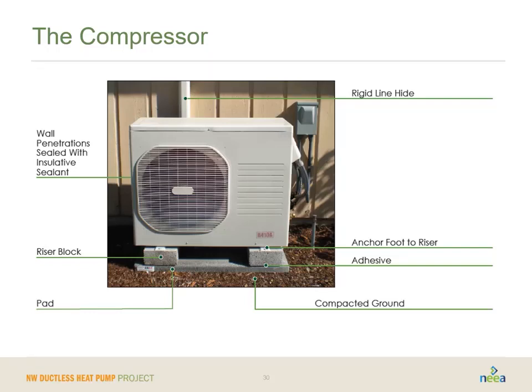Next, you want to use some adhesive to adhere any riser blocks and then anchor the foot to that riser. Again, there are various types of risers available. 2 or 3 inch risers are kind of standard. We prefer 6 whenever possible. That just gives you that little bit of extra benefit for when there's a lot of leaves or a medium amount of snow. If you're in an area with high snow on an annual basis or typical snow drifts, you may want to consider wall mounting the outdoor compressor.